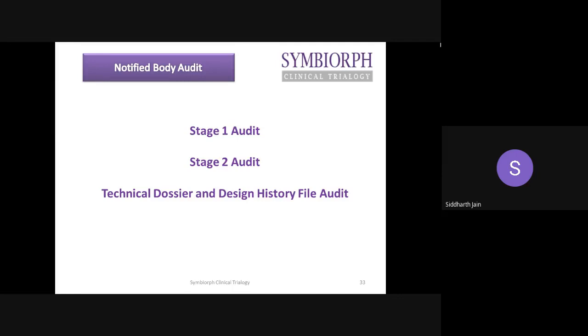So depending upon that, the stage 2 audit will be carried out for your quality management system as per the requirement of ISO 13485, plus an in-depth audit of your technical dossier. During that time, the auditor will give you major non-conformities, and we have to close these non-conformities as early as possible.